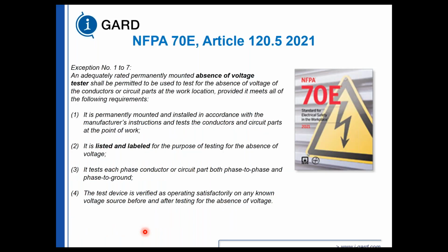Hence, NFPA 70E 2021. They put an exception over here, for which the note 7 is the same, but an exception to note 7 is: an adequately rated permanently mounted absence of voltage tester shall be permitted to be used to test for the absence of voltage. Listed and labeled, but they went on further and said it must be listed and labeled to UL 1436.